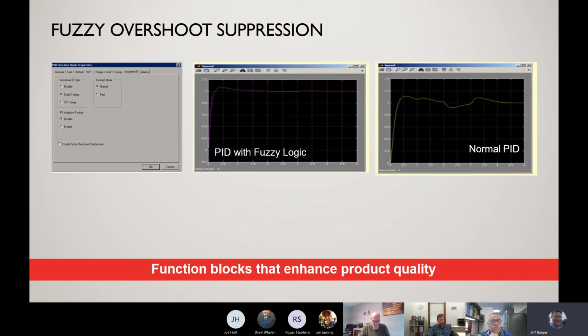This is an example of the PID with fuzzy logic. So you can see on the far right hand side, this might be pretty typical of a normal PID loop where you're coming up to temperature, and then once you start trying to line out at the set point, you might have some corrections that happen in the process controller in order to later on line out at your set point. On the left hand side, if you have fuzzy logic in some applications, it allows that PID loop to come up to set point and very, very quickly assess where it needs to be and lines out at set point very quickly. So this is fuzzy logic, which is a standard feature in the HC900, and you can either enable it or disable it, but it's a nice feature to have to increase productivity and quality.